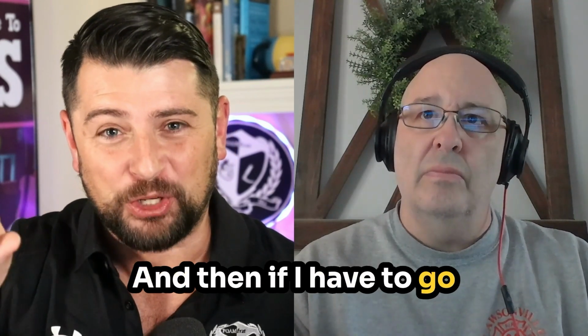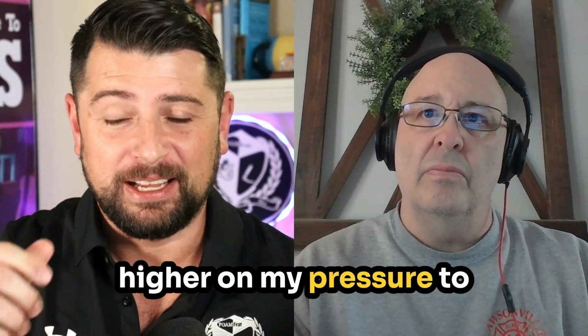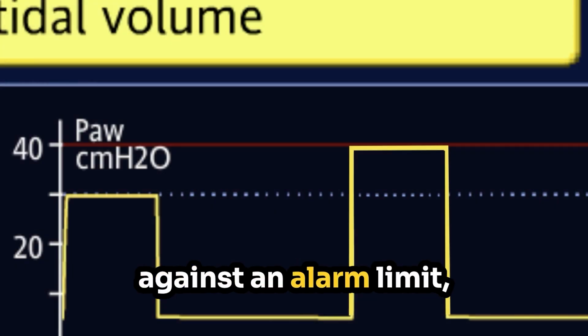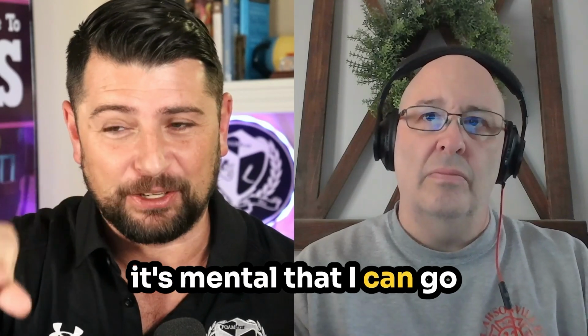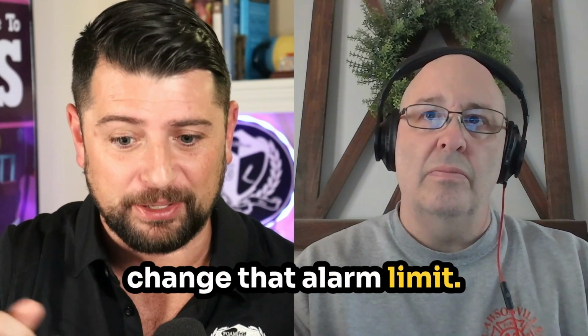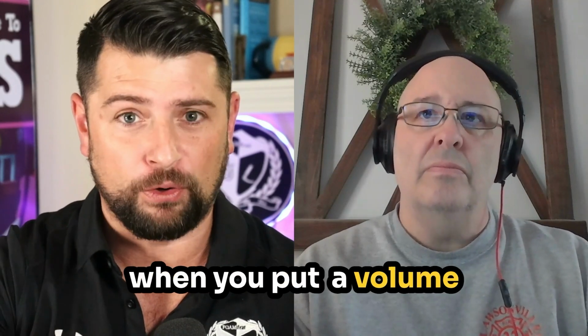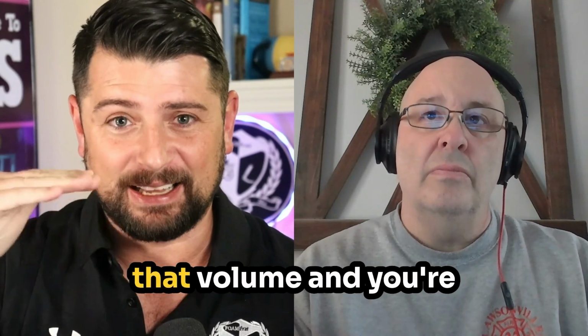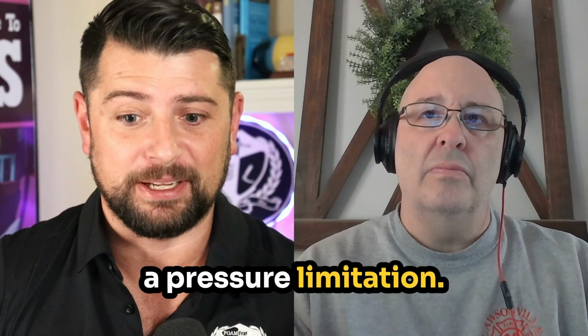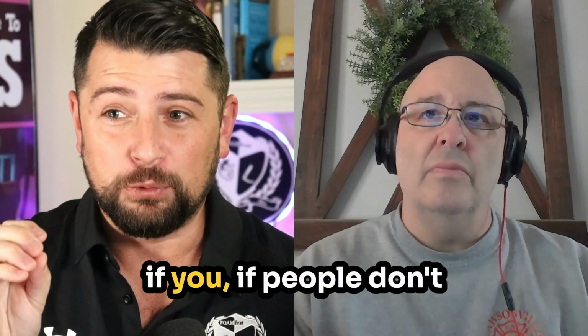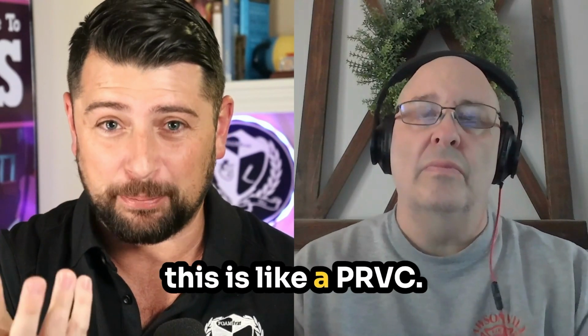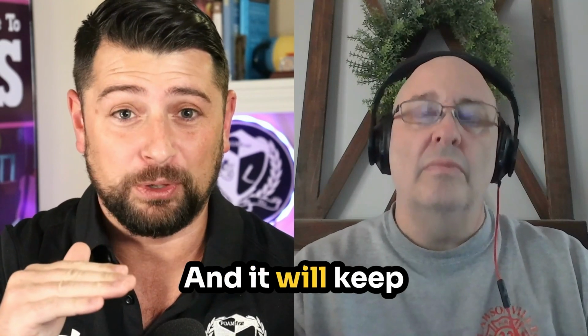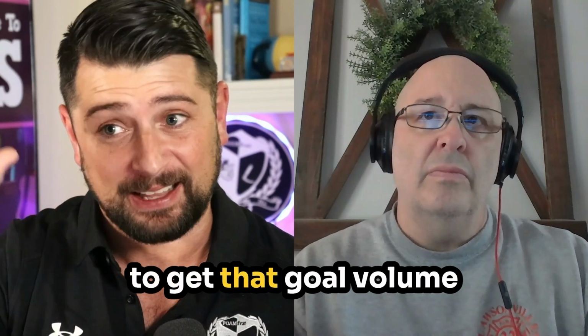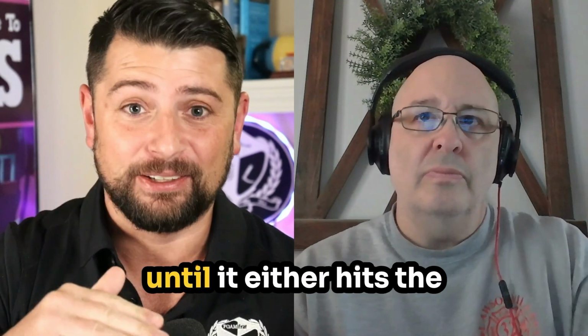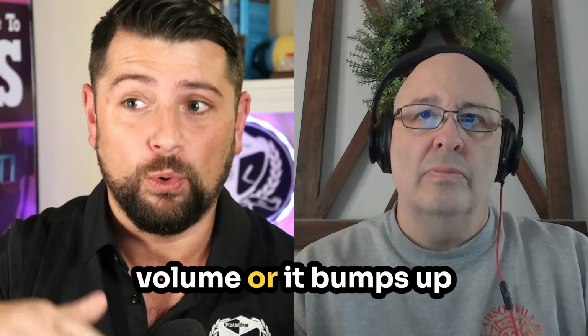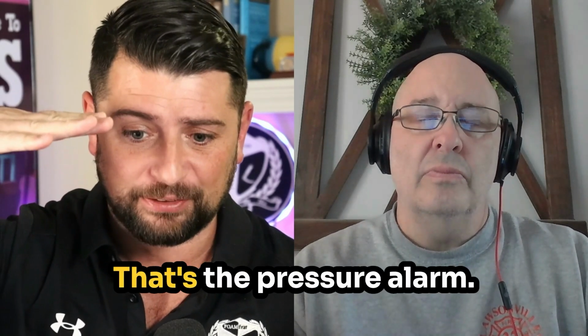And then if I have to go higher on my pressure to the point that it's bumping against an alarm limit, it's a matter of going in there and changing that alarm limit. Whereas I feel sometimes when you put a volume in and you're not hitting that volume, and you're seeing that you have a pressure limitation, I've seen people not understand that this is like a PRVC, and it will keep increasing that pressure to get that goal volume until it either hits the volume or it bumps up against that ceiling. That's the pressure alarm.